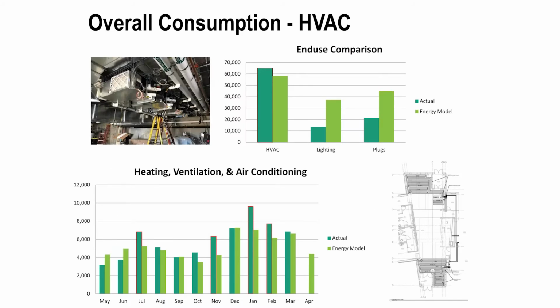We can see here that lighting's down and plug loads are down. Lighting, I don't think this was mentioned, but the lighting system not only interacts with the HVAC system and the set points, but the lighting controls are actually vacancy sensors. So if there's enough daylight in the space, users just aren't turning on their lights. There's an action required to turn those lights on, which is a really simple strategy, but really effective at keeping the lights off.